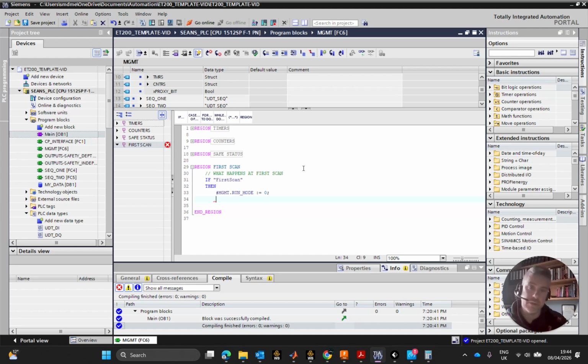So I'm going to be unsafe. Being unsafe will trigger some mode that's in the 9s, 9.1, 9.2, 9.3, which means maybe an e-stop is pressed, or the light curtain's pressed, or door interlocks open or something. Mode 6 is generally a recovery mode. So after I've come out of an emergency state, I've hit a reset button, nothing's happened, I might want to reinitialize or do a diagnostics check or do something. I'll use a different mode for that.